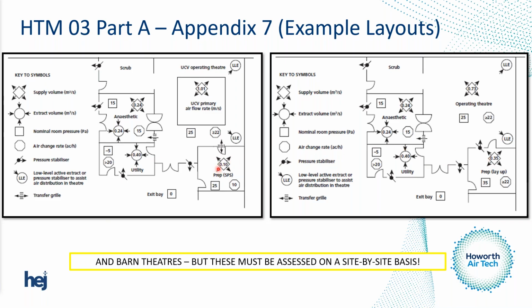which I'm not necessarily that bothered about in this presentation, but I need you to notice the pressure between the rooms. The pressure is 25 pascals in an SPS to the corridor, and 25 pascals in the operating theatre to corridor. In a layup prep room, it's 35 pascals to corridor, and it's 25 pascals to corridor in a conventional theatre. So with that in mind, if this is at the same potential or pressure as the operating theatre, this must be a transfer grill. The transfer grill is there to equalise the pressure. And in this instance, the pressure is higher, it's 10 pascals higher, so that must be a pressure stabiliser, which it indicates quite clearly.